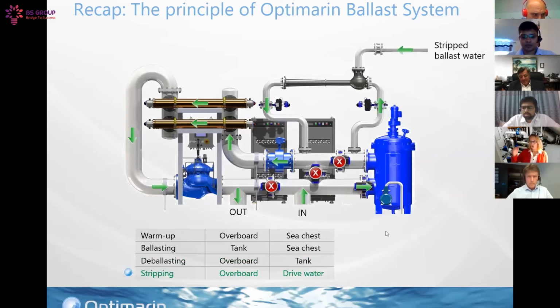Then you can also connect it to your stripping ejector. This is the vessel's stripping ejector. The drive water is run over the filter. It is not compulsory anymore. These days you can run it without filtration, but we always recommend to do it with, because first of all, you have better treatment, and secondly, you keep your lamps and your entire system cleaner.